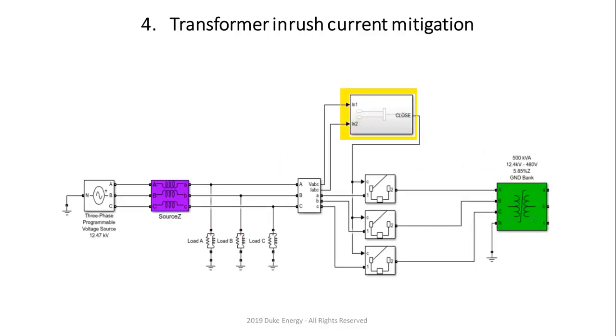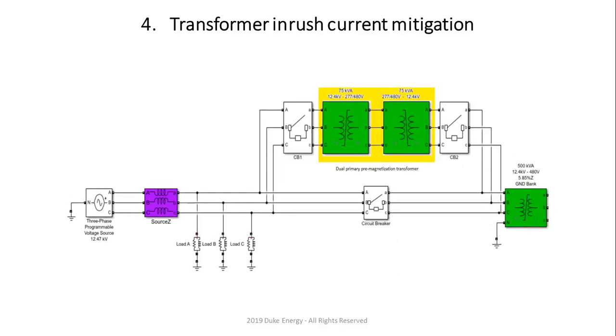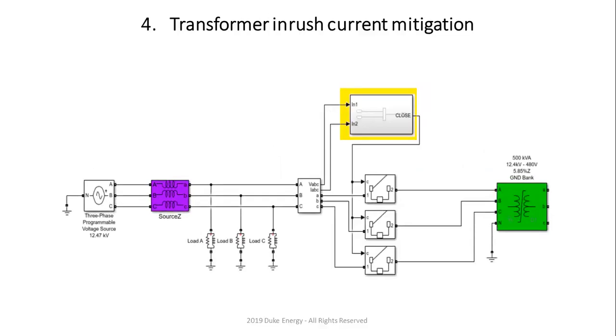Another option: what if we change this three-phase circuit breaker to single-phase, and then operate based on point-on-wave switching, because that can reduce current. That is true, but I did another analysis, and it showed that depending on your residual magnetism, even if you switch at 90 degrees, which is what you would typically want to do when switching on point of wave, you can end up switching with a higher inrush current. Now, just so you know, when you switch single phase, remember, between neutral and ground there's a CT.